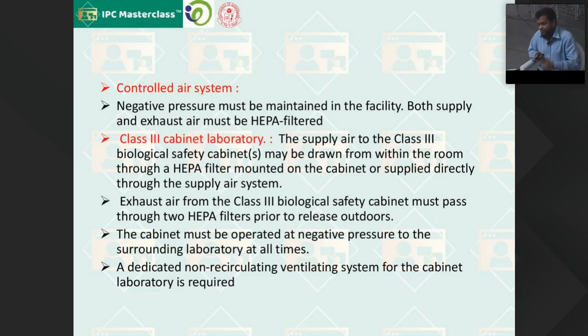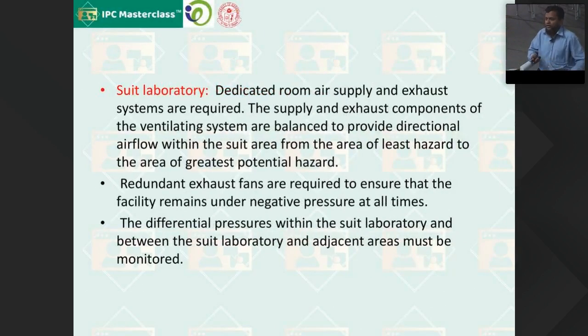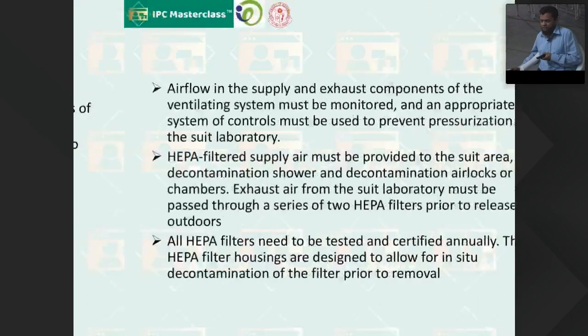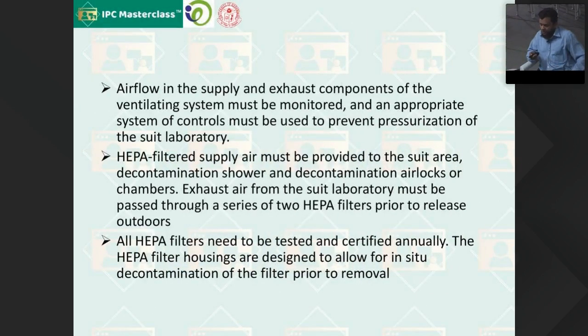Biosafety cabinet type 3, and exhaust air has to pass through the 2 HEPA filters, and it should be operated in negative pressure. Remember this point for the class 3 cabinet laboratory, because in a suit laboratory the requirement is totally different. We require only a dedicated room air supply with the exhaust system, and as I just told you, personal protective equipment with positive pressure HEPA filters inside, and unidirectional flow of air. Exhaust should maintain negative pressure at all times, and differential pressure between the suit laboratory and the adjacent areas should be monitored, because all the BSL-4 labs, whether cabinet 3 or suit laboratory, should be at negative pressure, with airflow in a similar direction.